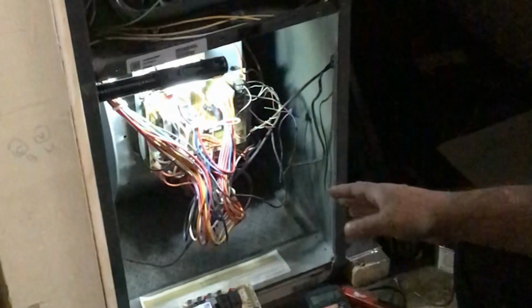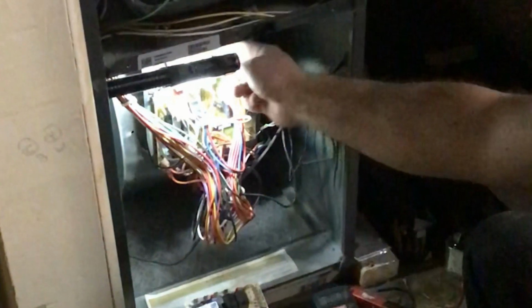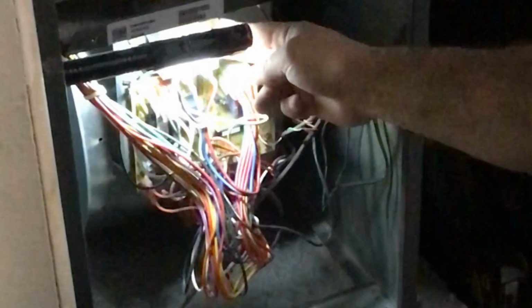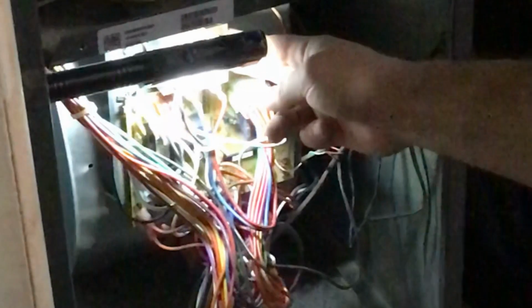All right, the 24 volt system all starts at your transformer, like we talked about earlier. So if you've got a 24 volt problem, you're not getting your 24 volts outside of your contactor. First thing you want to check, just like we did earlier, is do you have power coming into your transformer, and do you have proper power coming out? We talked about what to do in the last segment if you do not have power going to your transformer. So let's assume that we do. And obviously, if you do have power coming in, no power coming out, no 24, you've got a bad transformer.